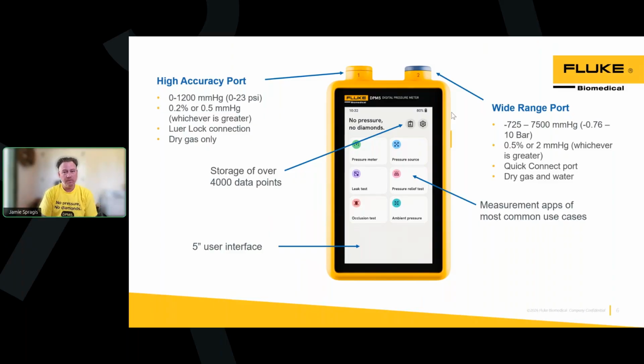Then port 2, that's going to be your wide range port. You also see the blue indication, that's going to do your water as well. So for all your occlusion pump testing, we'll go to port 2. And then your measurement apps, they'll follow the port that you're using, except for your pressure meter.